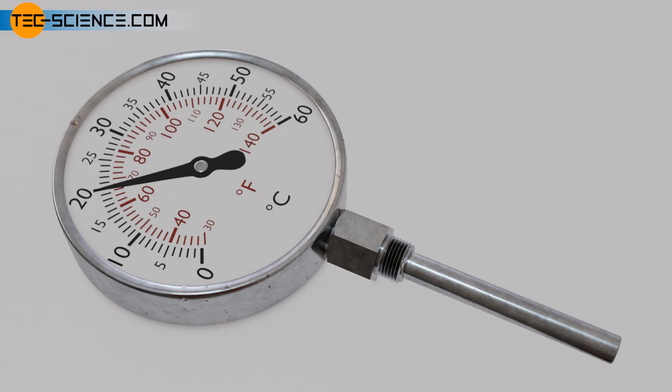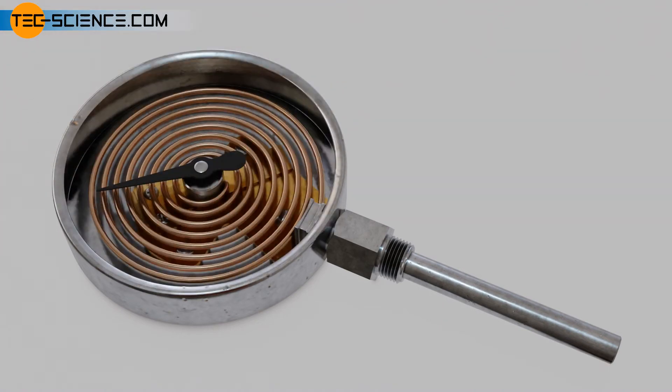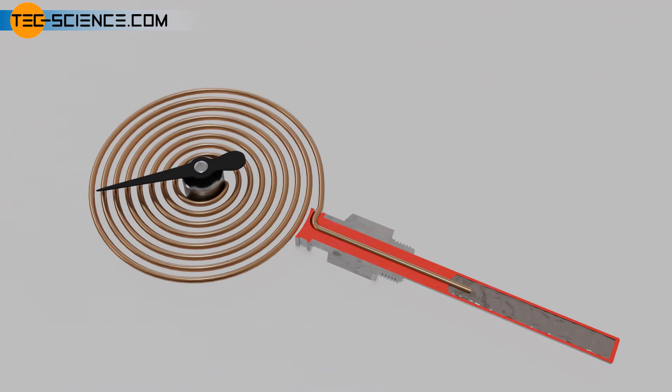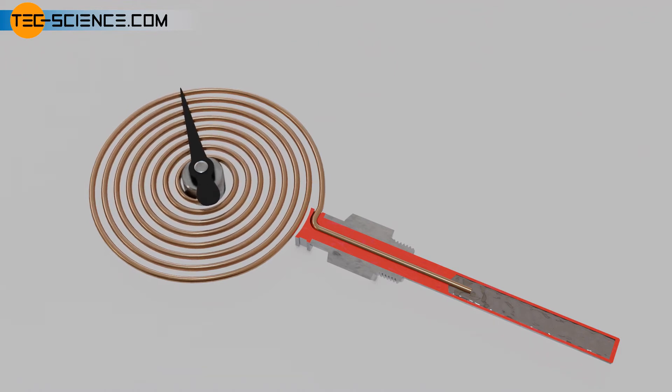In liquid-in-metal thermometers, a tube is wrapped into a coil and filled with a thermometric liquid to indicate the pressure rise. If the temperature of the liquid rises and with it the pressure, it tries to bend up the spiral tube like a spring. Such a tube is also referred to as a Bourdon tube.